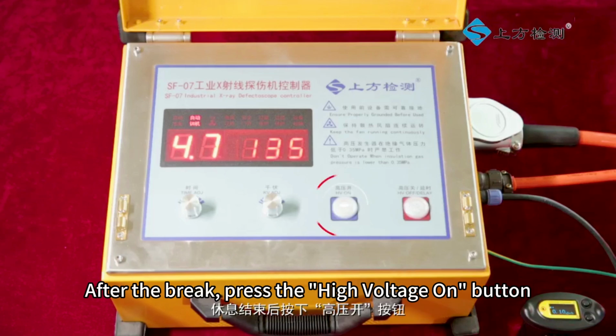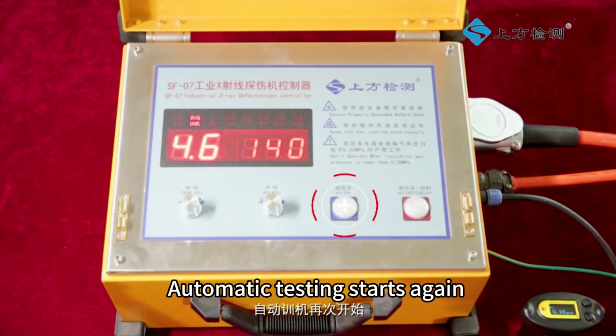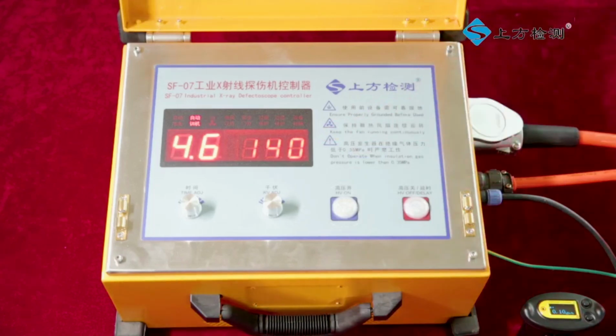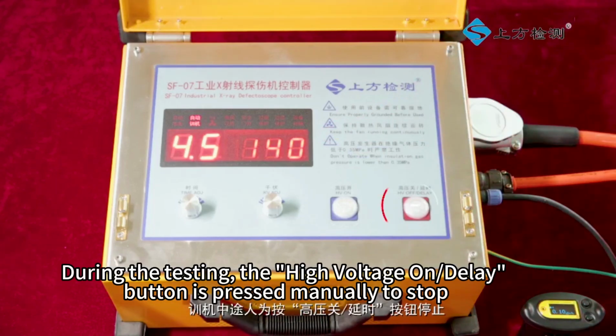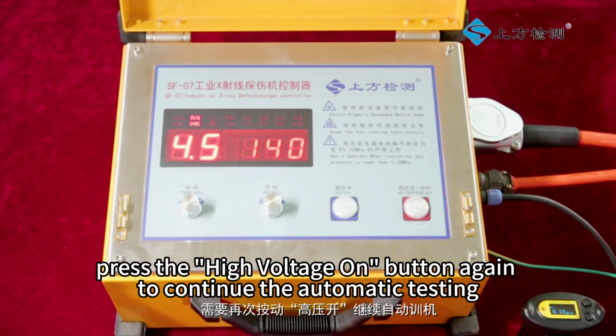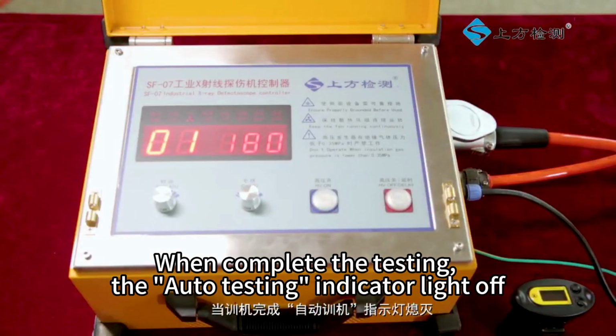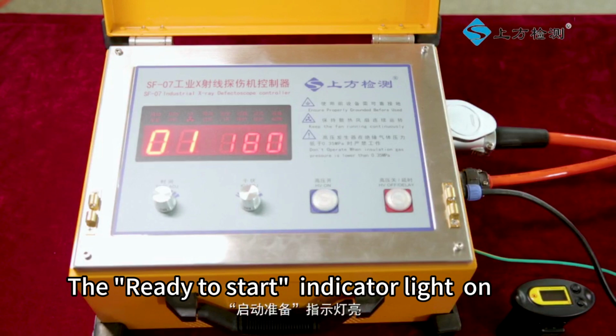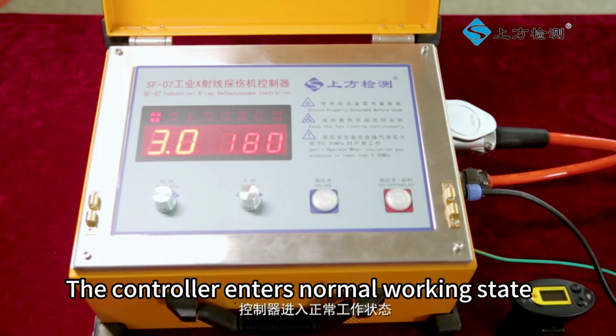After the break, press the high voltage on button. Automatic testing starts again. During the testing, the high voltage on/delay button can be pressed manually to stop, and press the high voltage on button again to continue the automatic testing. When the testing is complete, the auto testing indicator light goes off, the ready to start indicator light comes on, and the controller enters the normal working state.